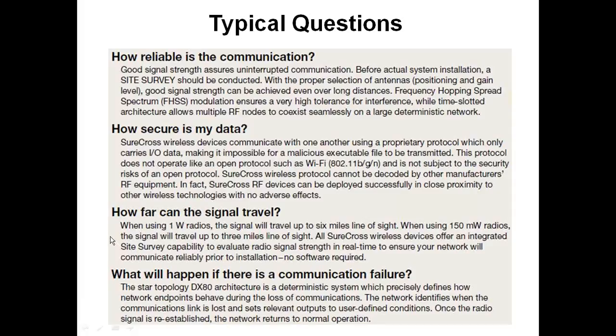Another question that comes up is, how far can I go? This depends on several parameters, but as I talk about the radios, you'll hear us talk about a 150 milliwatt radio and a 1 watt. What that means is if you're using a 150 milliwatt radio, we rate those 3 miles line of sight, with the standard 6-inch rubber duck antenna. If we go up to a 1 watt radio, we then rate those 6 miles line of sight, and you can penetrate some floors and walls. It really depends on what everything's made out of. But going back to that site survey, having the ability to do that will let you know how bad your signal's getting hammered if you do have obstructions in between.